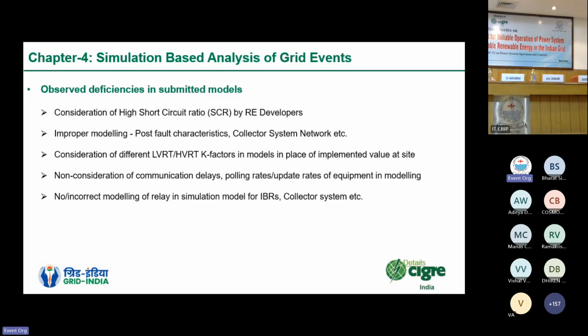Chapter 4, again, simulation-based analysis of grid events. What were the deficiencies noted from the submitted models? It was identified that a few developers had considered high short circuit ratios during their inverter tuning process, and those high short circuit ratios are not readily observed in the power system where they are operating as of now. In some cases, there was improper modeling, like post-fault characteristics. The time constants indicated different recovery rates of active power and reactive power, but here some different settings were adopted in the models.